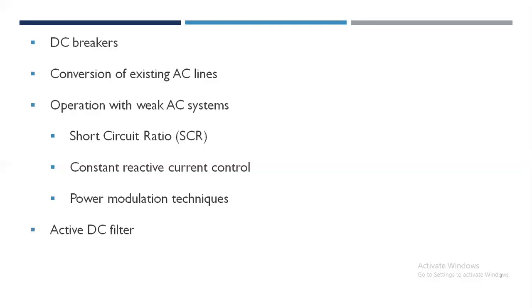Next concern is active DC filter. In the 90s, a hybrid filter made up of an active filter based on a voltage source converter in series with the passive filters was developed to improve the filtering of harmonic currents flowing in the HVDC lines. The active filters can eliminate both characteristic and low frequency non-characteristic harmonics. Both Siemens and ABB have supplied active filters. In India, the Chandrapur to Padghe HVDC project uses an active filter in each pole.